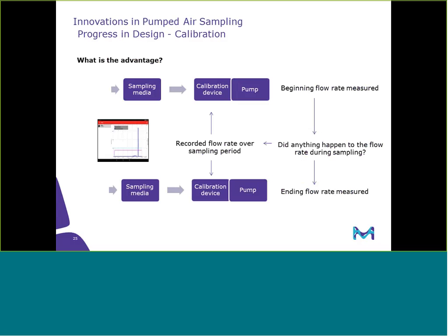So you're sampling media at the beginning, so your flow rate gets measured. Your flow rate gets measured at the end as normal, but in the interim, when it's sampling, when the person who that sampling pump is hung onto is being sampled, or that area where, if you're doing an area sample, where it's sitting, you walk away and have no idea what's going on with it. You obviously don't have a calibration device hooked to it, so you can't see what the flow rate is, or nowadays, some pumps do record some sort of a flow rate, but that's not a true calibrated flow rate because they don't have a calibration device that they measure that true flow rate with. So what we've done allows you to actually record and see what exactly is happening to your flow rate over that period of time.